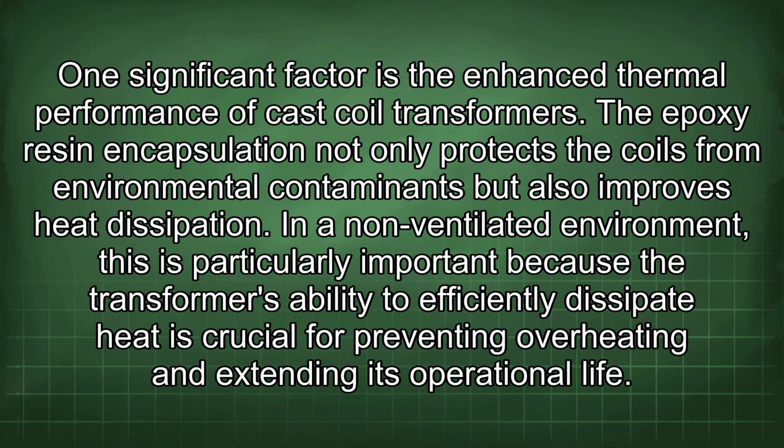One significant factor is the enhanced thermal performance of cast coil transformers. The epoxy resin encapsulation not only protects the coils from environmental contaminants but also improves heat dissipation. In a non-ventilated environment, this is particularly important because the transformer's ability to efficiently dissipate heat is crucial for preventing overheating and extending its operational life.